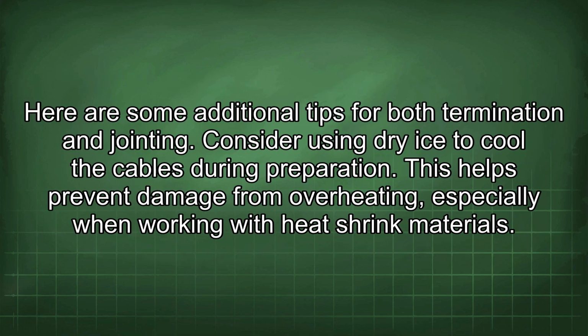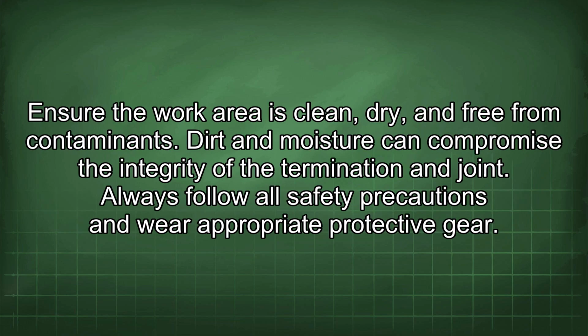Here are some additional tips for both termination and jointing. Consider using dry ice to cool the cables during preparation. This helps prevent damage from overheating, especially when working with heat-shrink materials. Ensure the work area is clean, dry, and free from contaminants. Dirt and moisture can compromise the integrity of the termination and joint.